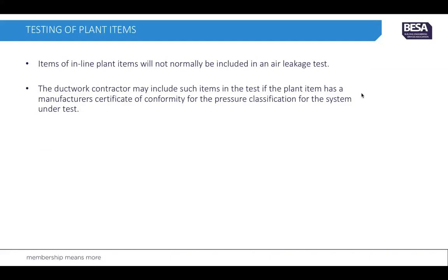The ductwork contractor may include plant items such as fire dampers or volume control dampers in the test, provided that the particular plant item has a manufacturer's certificate of conformity for the pressure classification of the system under test. However, this is unusual, and such items would often be excluded from ductwork testing.